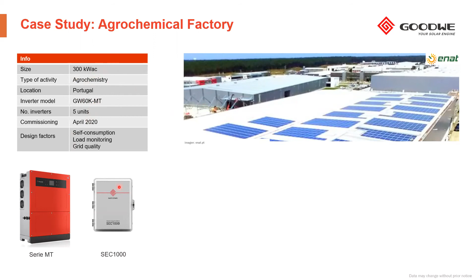This scenario is quite common. What we saw in that facility is that it's very common in commercial, especially in industrial scenarios like this case, the reactive power capacitor banks. Usually, we will see this kind of solutions to compensate the reactive power in the facility. That means that the quality of the grid inside of the facility is not the ideal one, right? And that has an impact, because if the quality of the grid in the facility is not good enough, the inverter or inverters could be affected. When they try to connect to the grid, to feed into the grid, if the grid parameters that the inverter monitors permanently are out of range, the inverter will wait until the grid is more stable, right? So this situation is quite common, less in commercial, but for sure quite common in industrial.